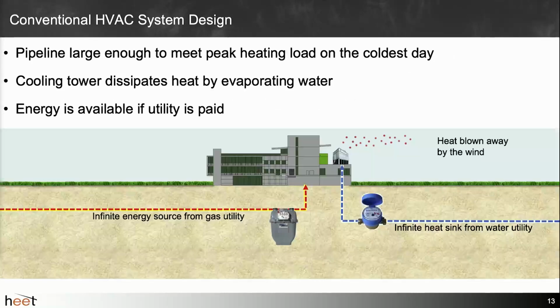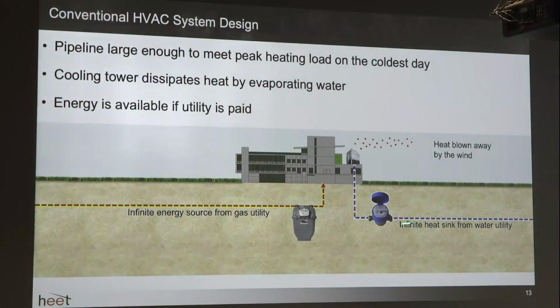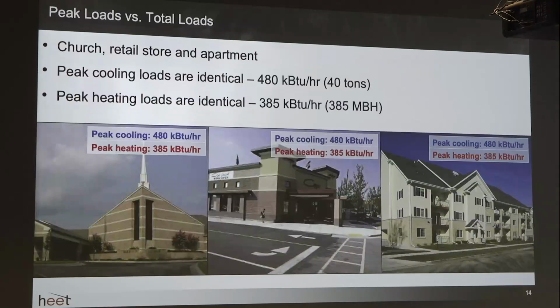And so in a conventional system, you have a pipeline that's large enough to meet the peak heating day, the coldest day of the year, right? You have your natural gas pipeline that's feeding that equipment. You have your water utility line that's feeding your cooling tower to dissipate heat on the warmest day of the year. And as long as you pay your energy bill, you should be okay. But for a ground source heat pump scenario, we are also concerned with our total loads, right? Again, because we're designing our source.